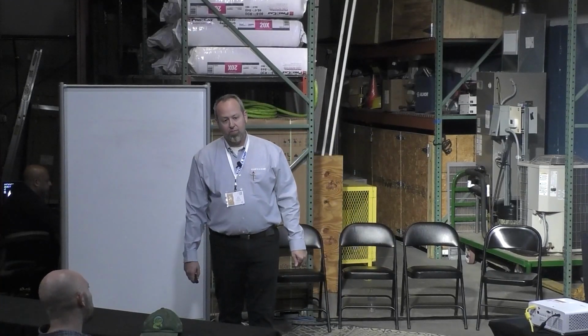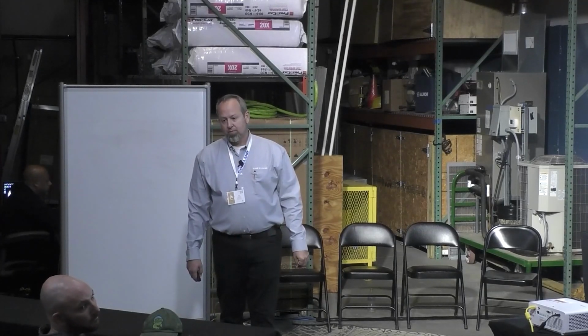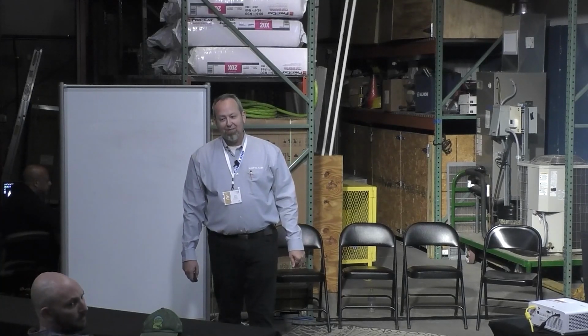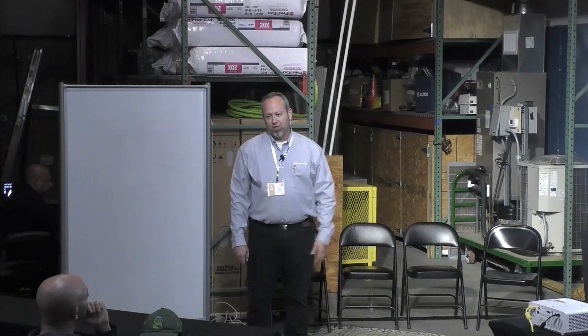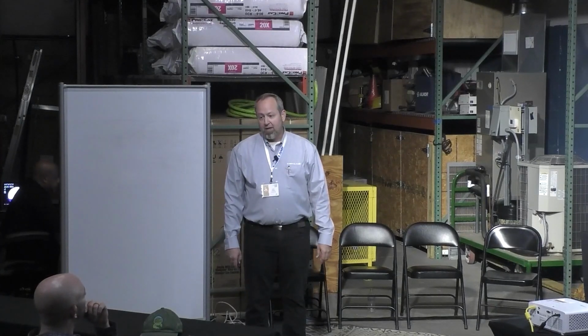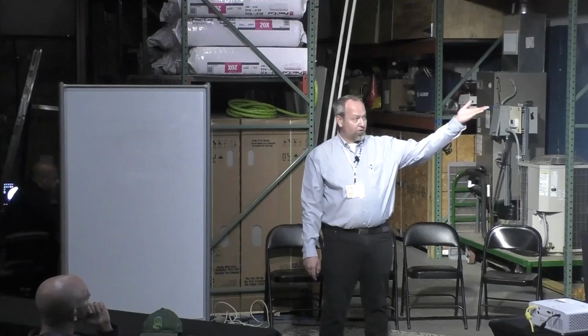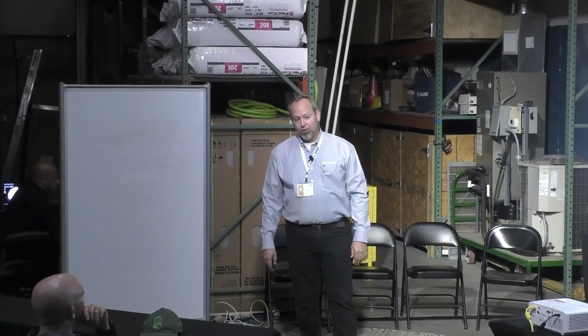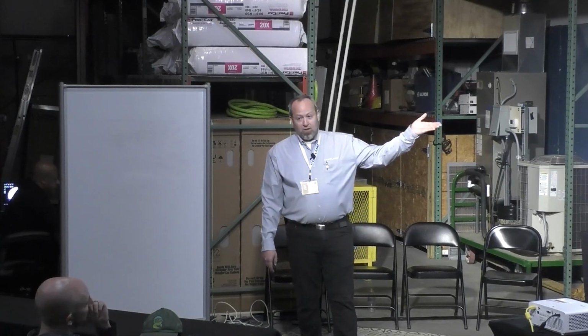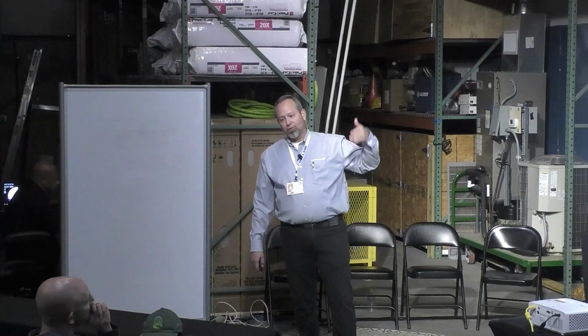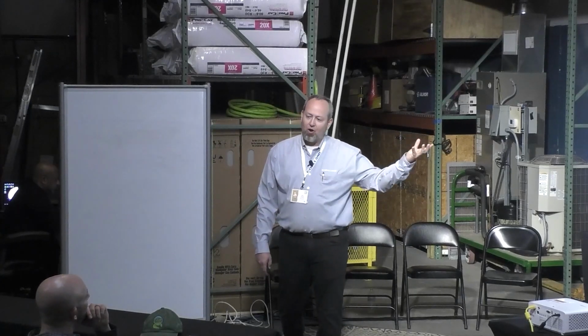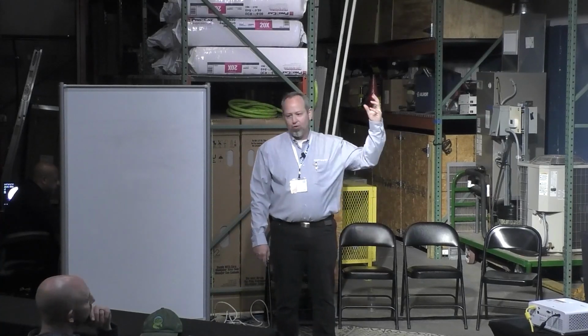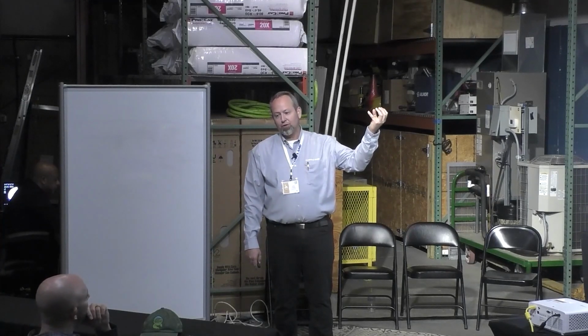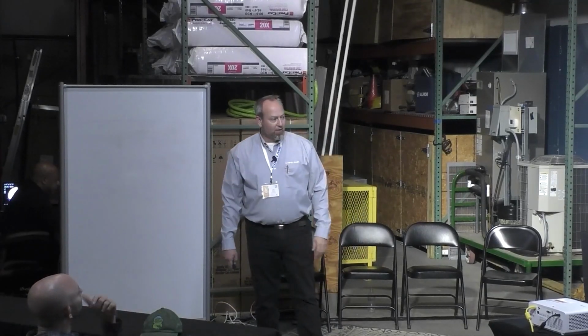Correct. Yeah, I've not seen the limit pop on that with the amount of time that it would take to switch with the two of them. So yeah, and a valid point. If your heat pump's running and you're kicking on your gas furnace, do you run that risk of running out on a limit? However, keep in mind that if your gas furnace is coming on second stage, your heat pump and fan are already running. So you're actually starting to cool that heat exchanger as soon as there's fire in it. You aren't building up temperature in that heat exchanger prior to the fan coming on. The fan's running through the whole cycle.